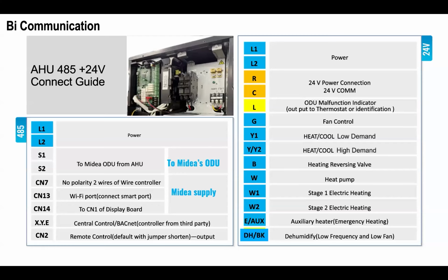R and C are your 24-volt power connections. The 24-volt connections are right here on the board. L is an outdoor unit malfunction indicator. That would wire from the outdoor unit all the way back to the thermostat to turn on the malfunction light on the thermostat. Probably not going to use it if you're not using 24-volt to the outdoor unit, because that's an output from the board on the outdoor unit.